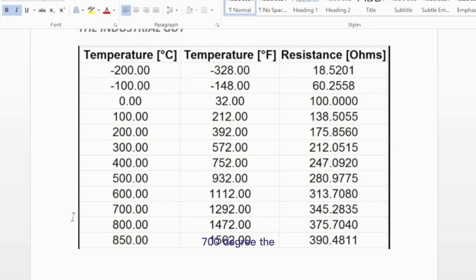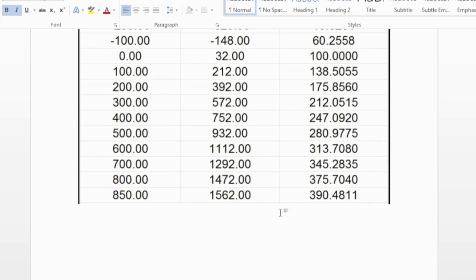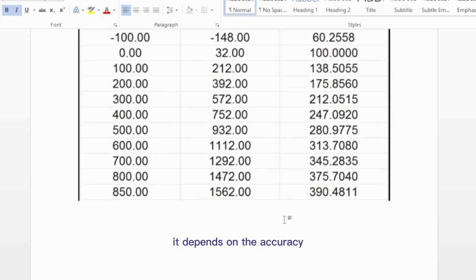At 700 degrees, the PT should give us a value of 345.28 ohms. If the value is plus or minus 2%, there's no problem with the PT - it depends on the accuracy.